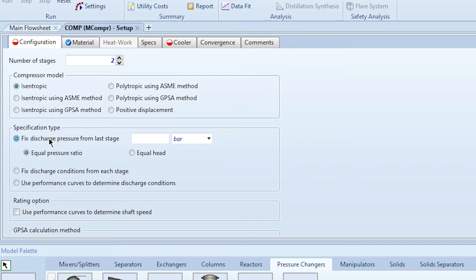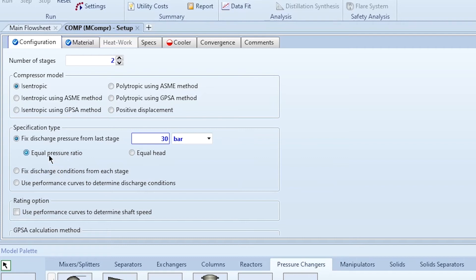We will select Fixed Discharge Pressure from Last Stage, set to 30 bar. There are also two distribution options: Equal Pressure Ratio and Equal Head. We typically select Equal Pressure Ratio, which means the compression ratio is the same across all stages. For example, if the inlet is 1 bar and the compression ratio is 2, the outlet of stage 1 is 2 bar, and the outlet of stage 2 is 4 bar — so 4 divided by 2 gives a pressure ratio of 2 for each stage.